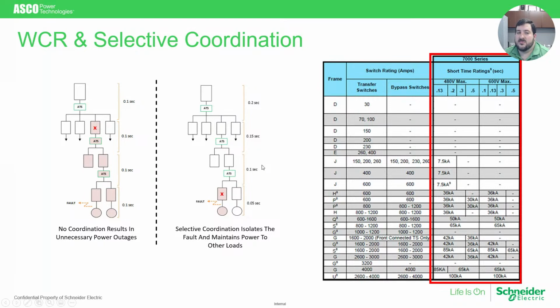So you need to make sure you selectively coordinate, and that has many advantages. If you do not selectively coordinate, you can over-engineer a project, get a transfer switch with an extremely high rating for an extremely long duration, but that will be a very large and very costly piece of equipment. Selective coordination not only minimizes the loads you take offline in a fault, but also allows you to use properly rated equipment for your application, allowing you to use more cost-effective and smaller footprint equipment, because you're not over-engineering for the largest and worst case possible scenario. So that's a very important topic to keep in mind.